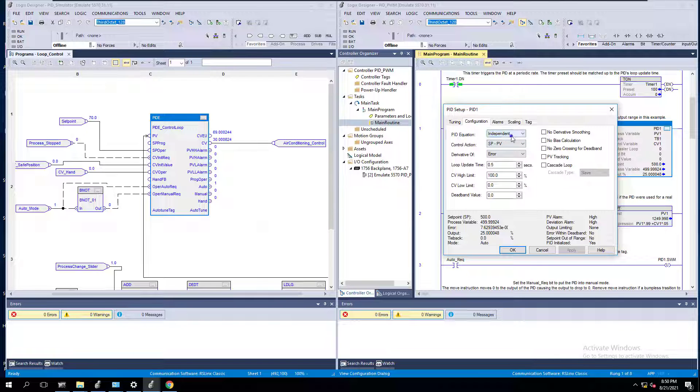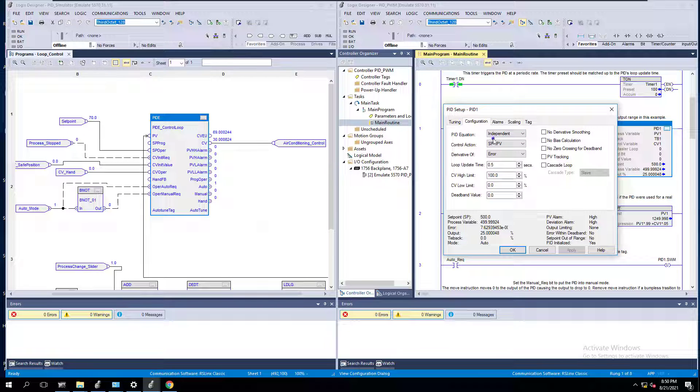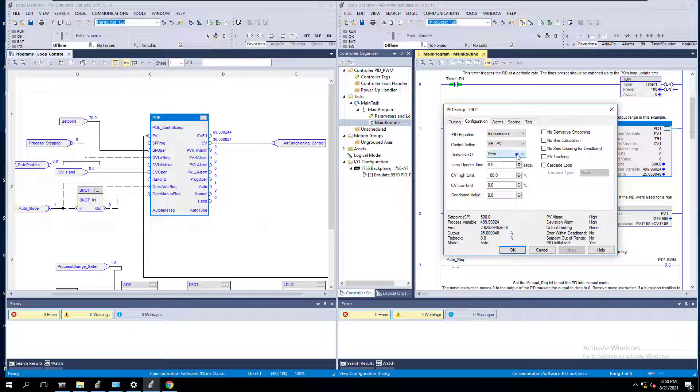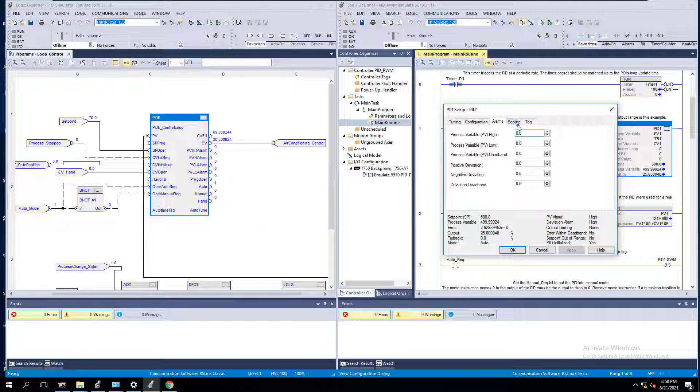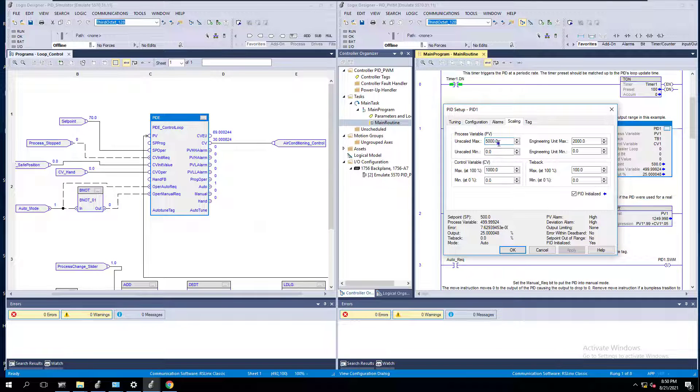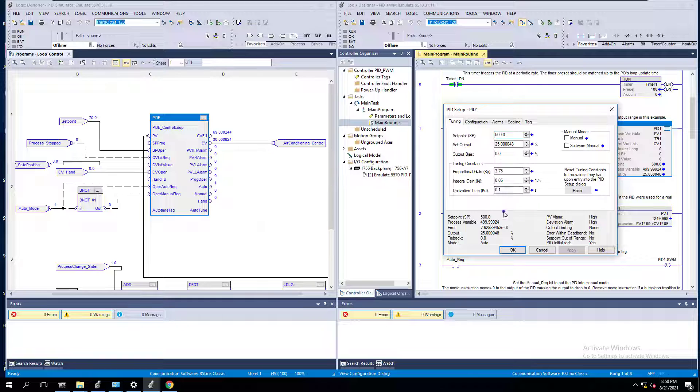Another one is your PID equation. Is it going to operate in independent or dependent? What controller are you going to use? Setpoint minus PV or PV minus setpoint? You're going to have the derivative off of error or PV. And then you have alarms and scaling. The key component is here, you don't have something called auto-tune. In Studio 5000, you don't have the ability to auto-tune.